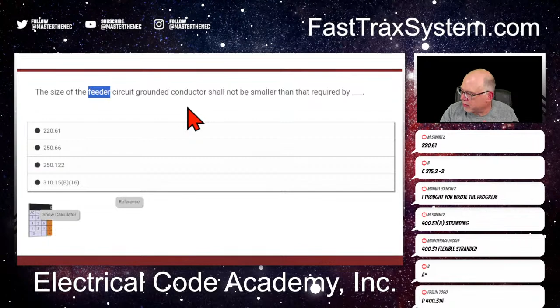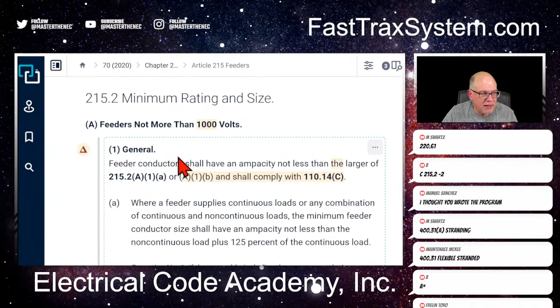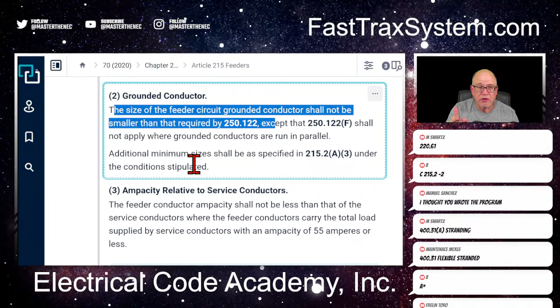Okay, and we'll go to the beginning here. All right, so this is at the very beginning, and we're talking about minimums, rating, and sizing feeders. Again, not over 1,000. Okay, and we scroll down, and boom, right away you see grounded conductor. It says the size of the feeder circuit's grounded conductor shall not be smaller than that required by 250.122. Okay, so again, it's a feeder, so it's got an overcurrent device ahead of it, so it can't be smaller.